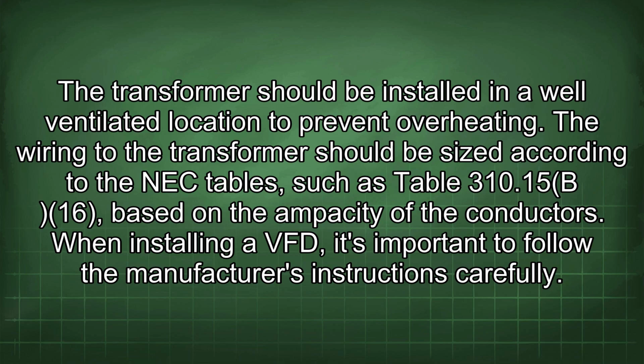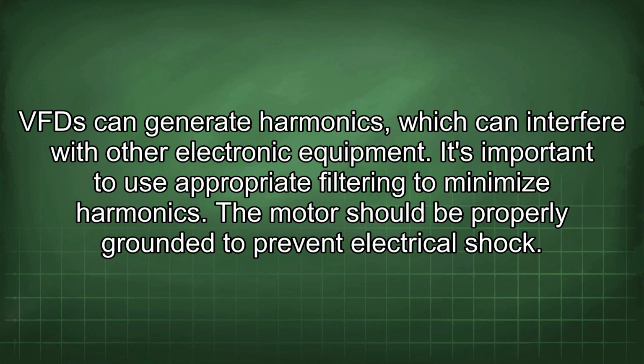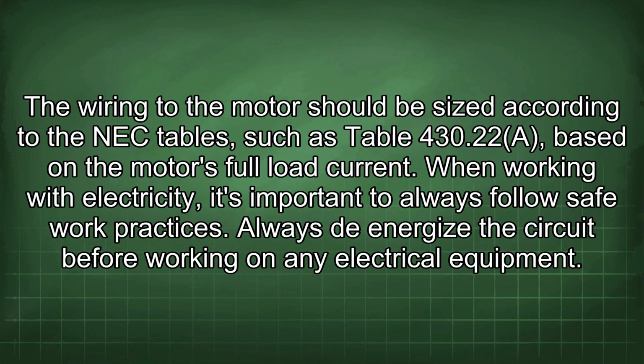When installing a VFD, it's important to follow the manufacturer's instructions carefully. VFDs can generate harmonics, which can interfere with other electronic equipment. It's important to use appropriate filtering to minimize harmonics. The motor should be properly grounded to prevent electrical shock. The wiring to the motor should be sized according to the NEC tables, such as Table 430.22(A), based on the motor's full load current.